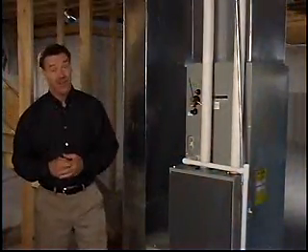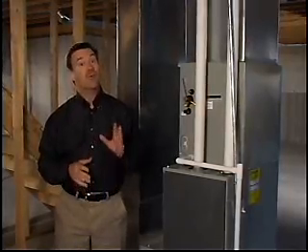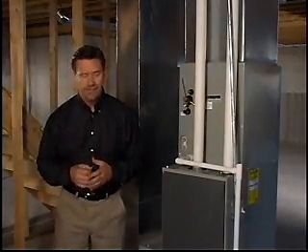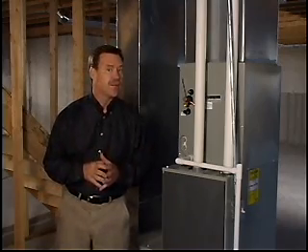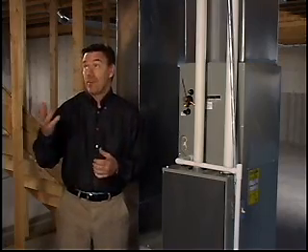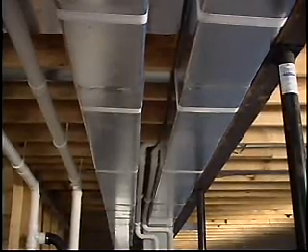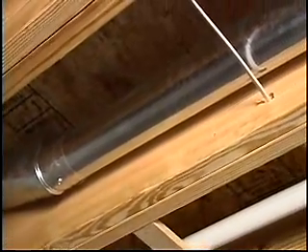You may be surprised to know that how you install your heating, ventilating, and cooling system can also contribute to moisture problems in a home. The average home has about 300 to 400 CFM of duct leaks. That's due to the fact that ducts inherently are leaky, and as that air exfiltrates out, for example here we're in a basement, if we have the ductwork located in a basement, that tends to create a positive pressure in the basement because of the duct leaks. But upstairs, that area tends to be under a negative pressure.